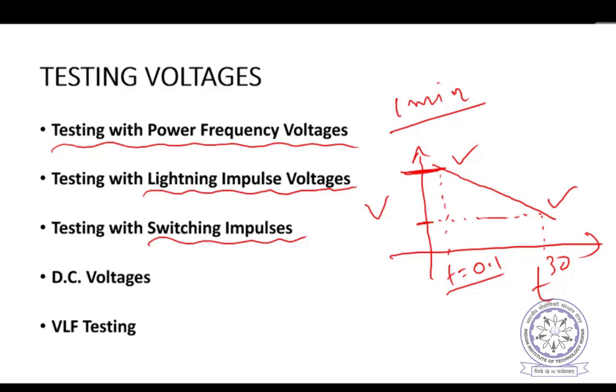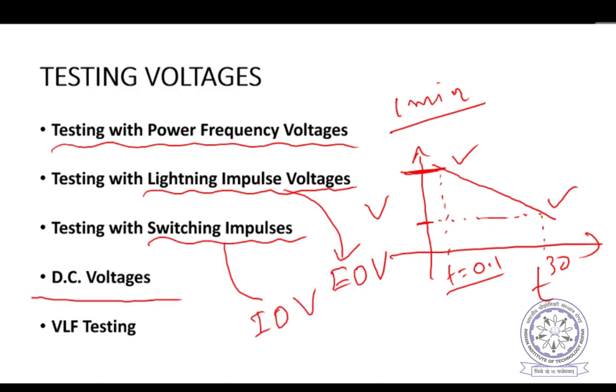As I already told you, lightning impulse is the external over voltage, and switching impulse is internal over voltage. Apart from these, tests will also be carried out with DC voltage. For example, consider a very long cable. Such a very long cable is actually a cylindrical capacitance, so it will absorb a lot of reactive power. So at power frequency, even though I am talking about an AC cable, we need to test under DC voltages also.